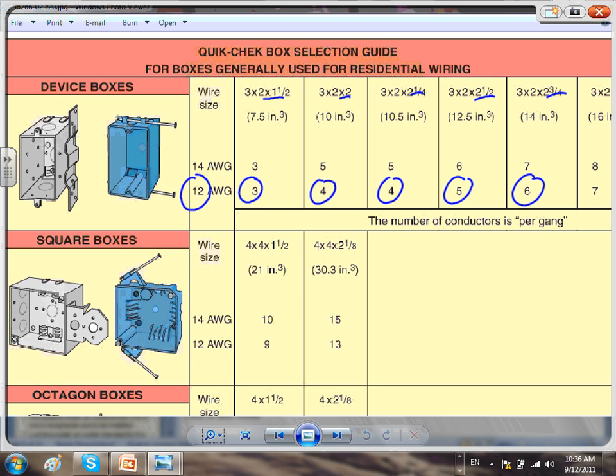So if you get into a situation where the inspector is upset because you exceeded the box fill, and you're using a 3x2 by 1.5, what do you do to make him happy? Go deeper - change it into a deeper box, so you get more conductors. You guys are familiar with this, we've seen it before.